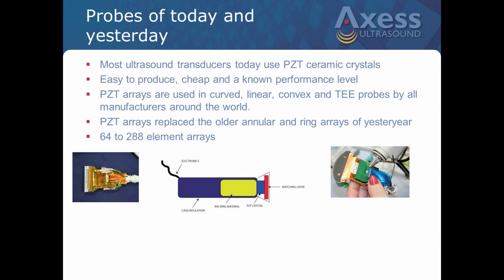PZT arrays are used in all probes. As you can see, curved, linear, convex, transesophageal probes as well. And every manufacturer on the planet uses them. PZT arrays are actually an enhancement from some of the older annular and ring arrays of 20 years ago. One of the things on PZT arrays, ceramic arrays, is that they do have a limited amount of elements. They go typically from 64 elements, which you'll find in most transesophageal probes, to up to 288 elements in some of the multiplexed linear probes. So there is a limit as to how many elements they can actually have with this type of probe technology.